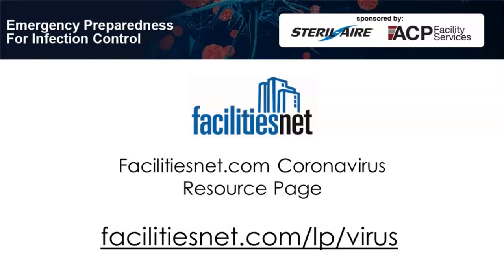Would UV be effective in HVAC applications with air velocity at 500 feet per minute and above, and what residence time is needed for it to be effective? Yeah, so it depends on, again, the strength of your UV system. I can give you an example that, in a typical Steril-Aire system on a 50-inch by 70-inch system, we designed to a very specific energy field for mold-based organisms because they're much harder to disinfect. And removing the biofilms on coils, there's also an energy savings component and the ability to remove HAIs, hospital or healthcare-acquired infections. So typically, across our emitters on a given second could be anywhere from 30 to 40,000 microwatts. When determining flyby at 500 feet per minute, you're going to get probably 0.2, 0.3 seconds.